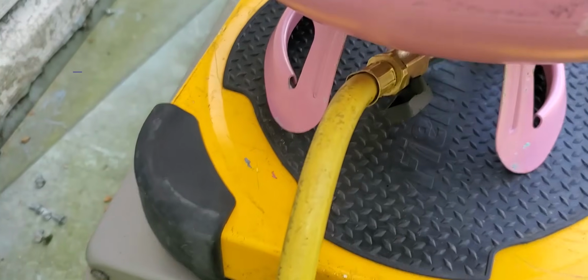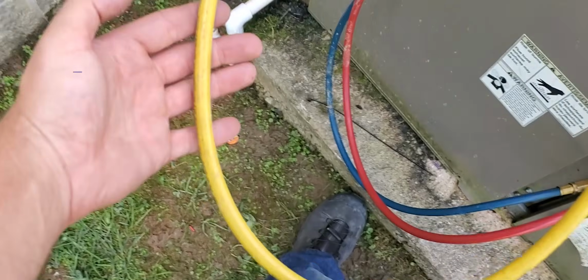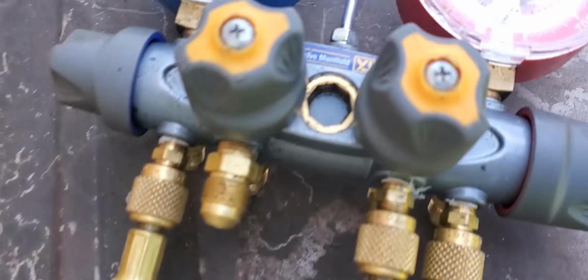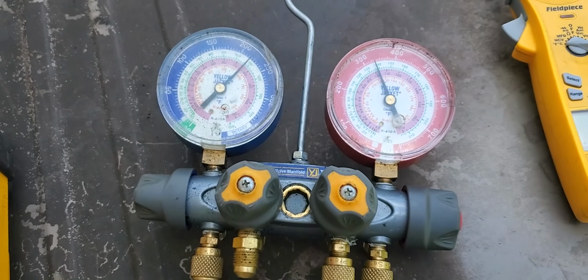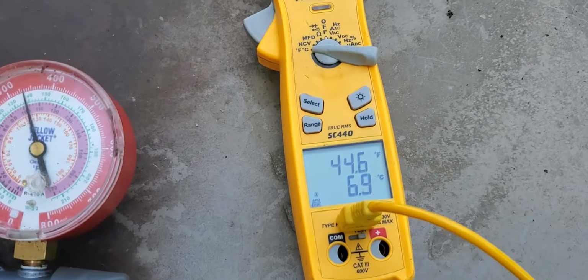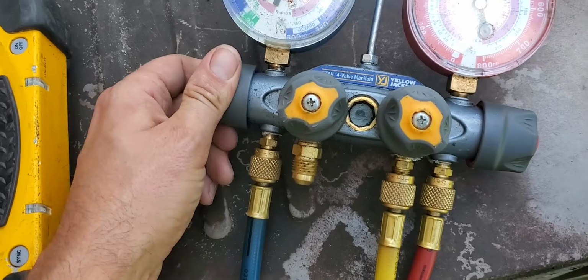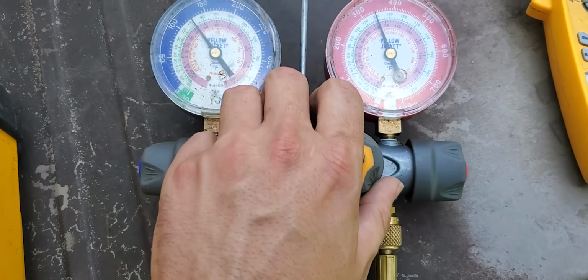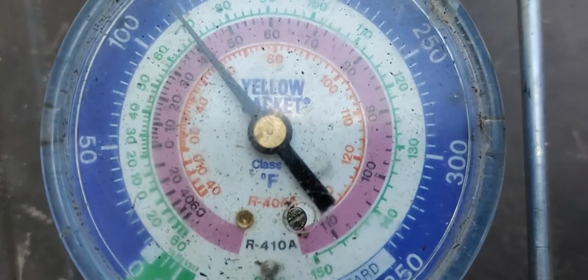Record the dry bulb temperature. Look up the target superheat for the system based on the temperatures of the ambient air outside and the return air inside. Record target superheat. Now, take an evaporator low side pressure measurement using the blue low side gauge.